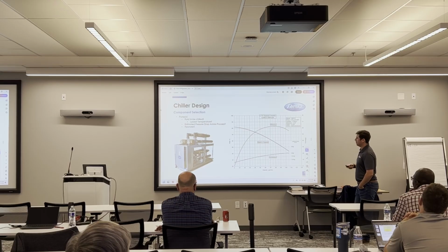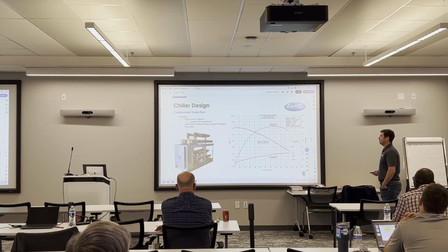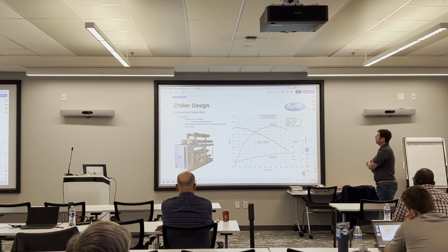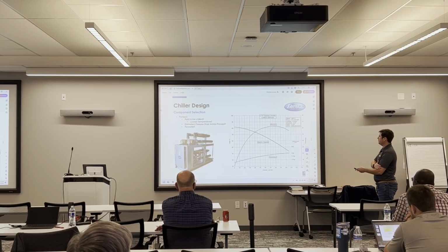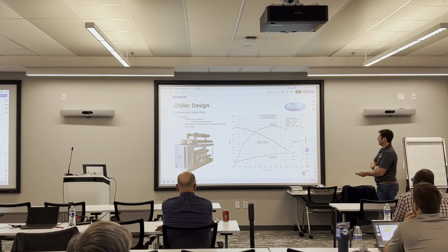When we figure out a customer's pressure drop across their equipment, we factor in the pressure drop from our equipment. We have a total pressure drop, which allows us to figure out what their best pump would be. So if they tell me they need a pump that does 70 GPM at, we'll say, 60 feet of head, well, this 2 horsepower pump would be the right one to go with. Just to talk about some of these curves real quick. This is our horsepower curve. As you increase your flow rate, you're going to yield a higher horsepower from that pump. The curve sloping down represents the actual performance of the pump.